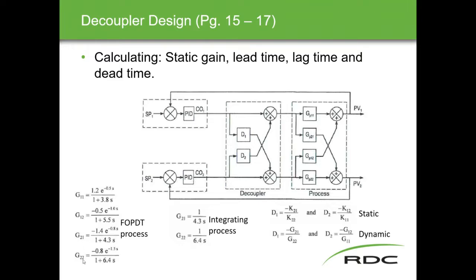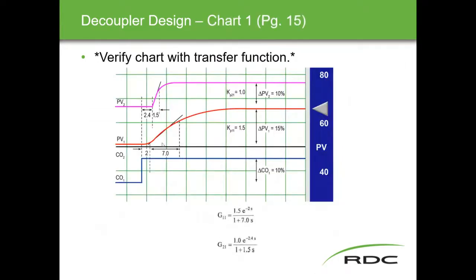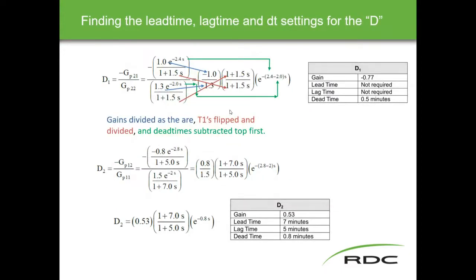These numbers are process-related, derived from tests: PV1 with controller one, PV1 with controller two, PV2 with controller one, PV2 with controller two, and so on. We start with step response charts just like before to get the transfer functions. A 10% controller output change producing a 10% PV change gives a gain of one; a 10% change producing a 15% change gives a gain of 1.5. Draw your tangent line, find the 63.2% point, and get all your values to fill in the transfer function.